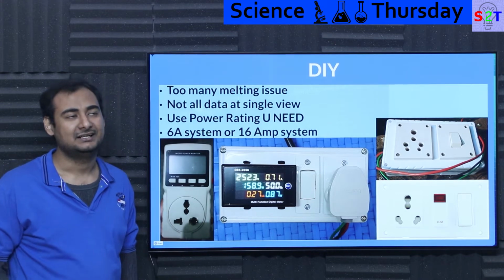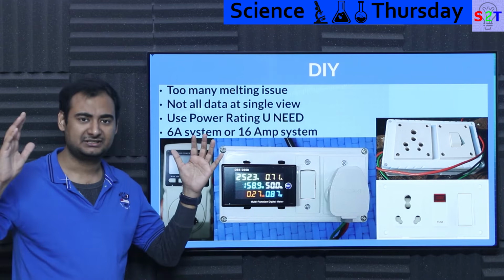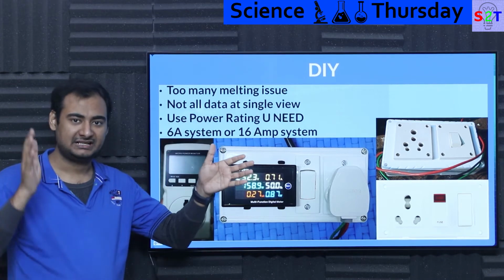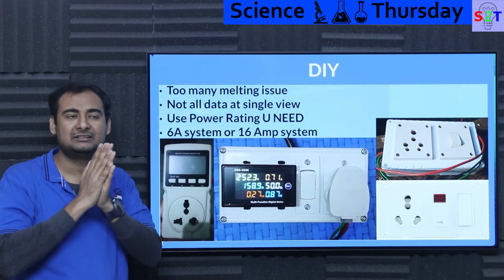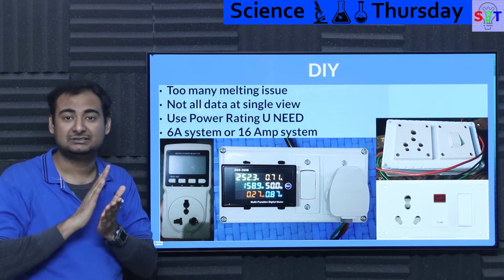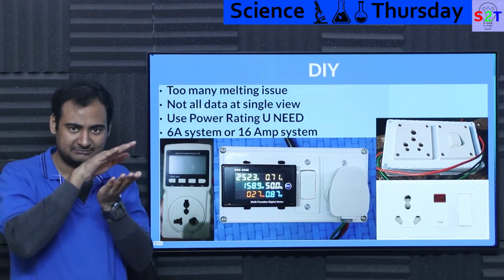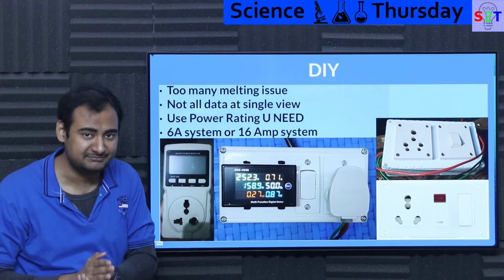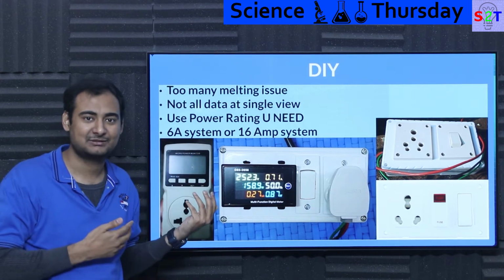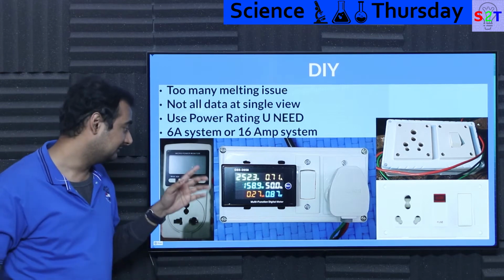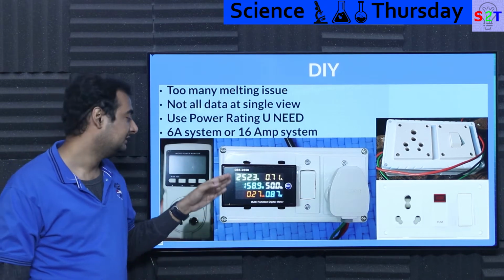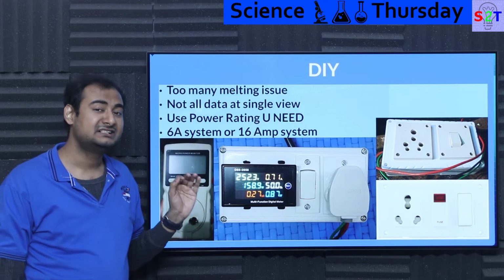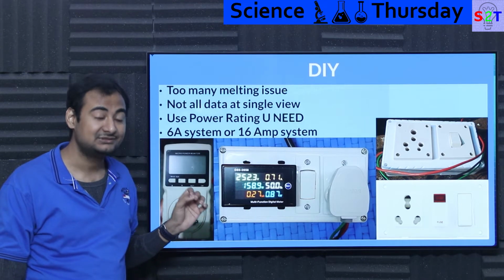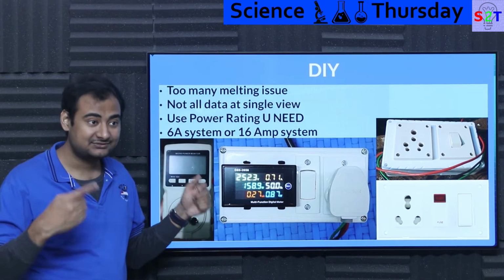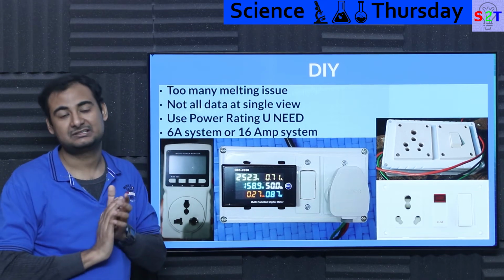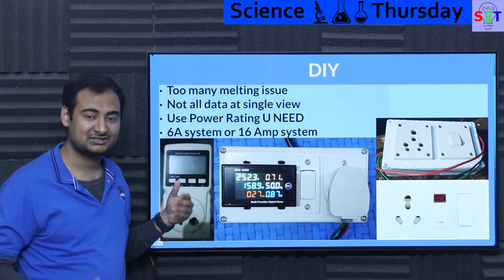Then I realized there's a period between summer and winter where it's cold enough that nobody turns on their fan, but not cold enough for anyone to turn on their heater. At that point, there's a serious drop in power demand, but the power supply is still working at roughly the same capacity as summer, so you get a voltage rise. This shouldn't happen, but it does - voltage in my area was reaching 260 to 270 volts, when it's supposed to be 220. Because of this, my UPS was stepping down the voltage, which caused the transformer to heat up, so it ran its fan to cool it down.